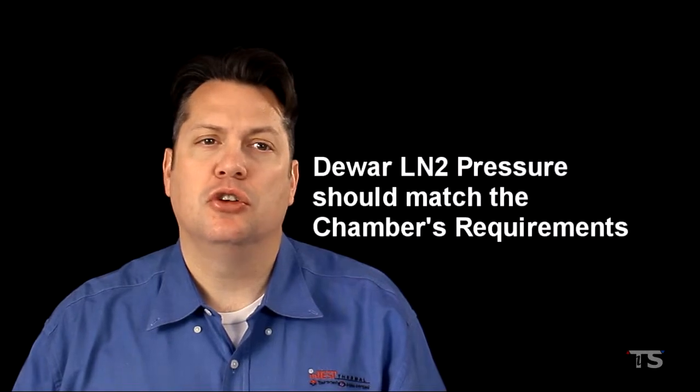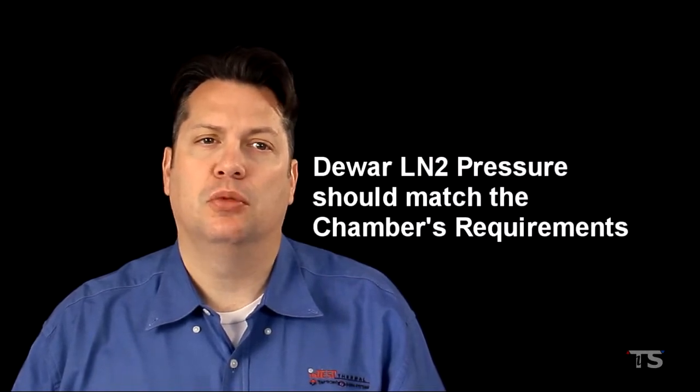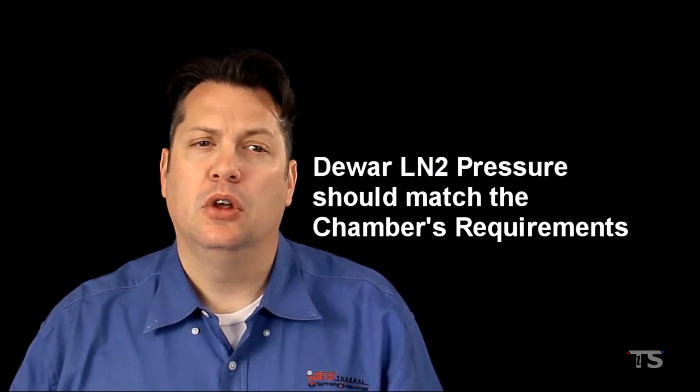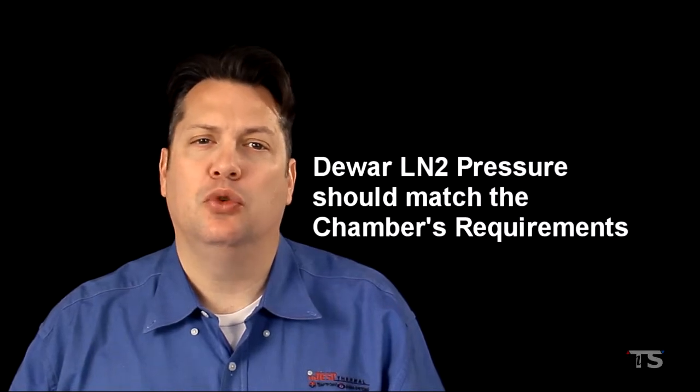Your Dewar's LN2 pressure should already be set to match your thermal chamber's pressure requirements. We discussed setting your Dewar pressure earlier in this video training course.